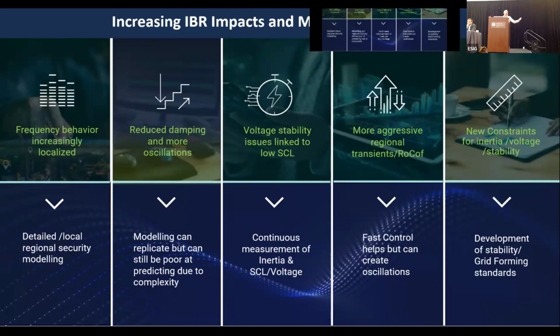So if your system is 1,000 miles across and you have the power loss at one end, the frequency response there will start responding within 500 milliseconds. Meanwhile, that frequency transient is only halfway across the system because it's traveling 500 to 1,000 miles a second. By the time the frequency transient arrives at the other side, the frequency response there has already responded, and that transient is now coming back across the system as well. Then this one comes back and they overlap. This is not a simple case of frequency being the same everywhere.